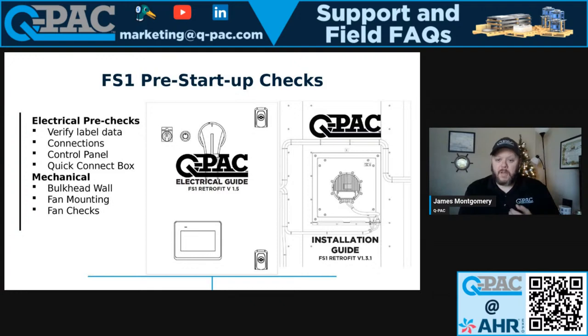Next thing, fan mounting. Each one of our bulkheads comes with a ledge. That ledge is specifically designed for someone to be able to rest the fan upon, push it into place, and tighten either 8 or 10 bolts. Those can easily be done. What I always suggest people do is make sure all those bolts are intact, take a quick look at the fans, do a visual inspection, spin the fan, rotate it. It's not powered up, so you're not going to hurt anything. You want to make sure that it's not making any noises, any grinding, any bearing sounds.